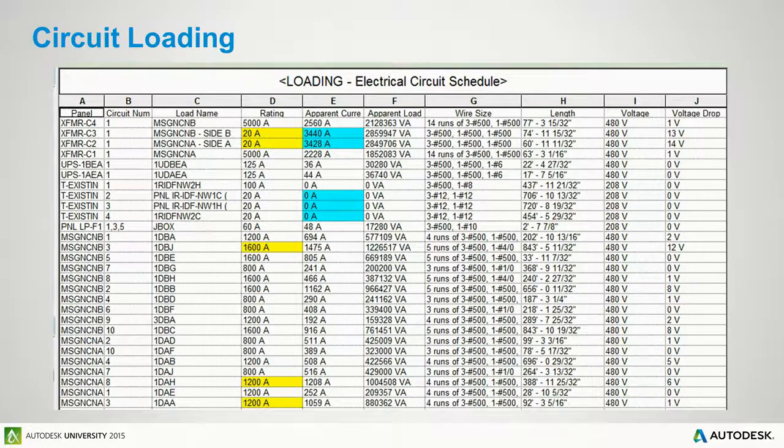So Revit understands that the panel is mounted at 3 feet, and it's going to go up to the ceiling, and it's going to go over, and it's going to go back down. So it does incorporate some of those ups and downs and 90-degree bends. However, Revit assumes everything is connected in series, meaning end to end, every light fixture 1 is connected to light fixture 2, which is connected to light fixture 3. Most of the time, a contractor is going to come out of your main electrical room, he's going to hit a junction box, and he's going to splice in that junction box to connect to the different rows of light fixtures. So now our circuit is actually not as long as Revit thinks it should be.